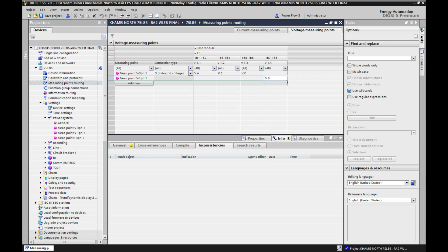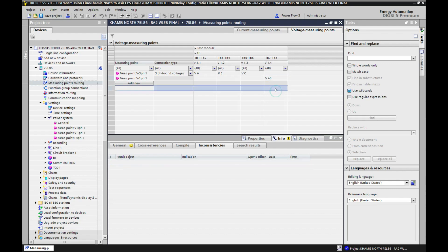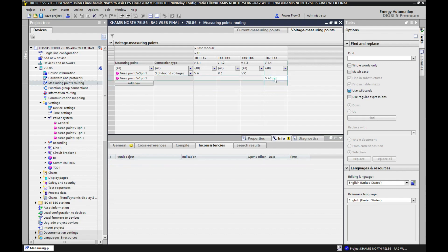Here we have different options — we are using this point for the bus VT. From here we can select, for example, the bus which is single phase. We can connect Va, Vb, or Vc — whatever is available. If our bus voltage is line-to-line, we can change it — for example, Vab — so it will take Vab between line to line.